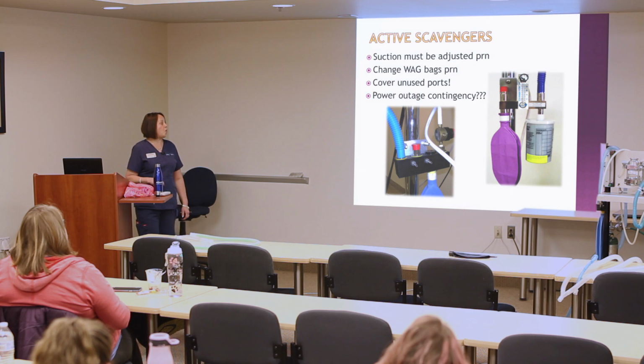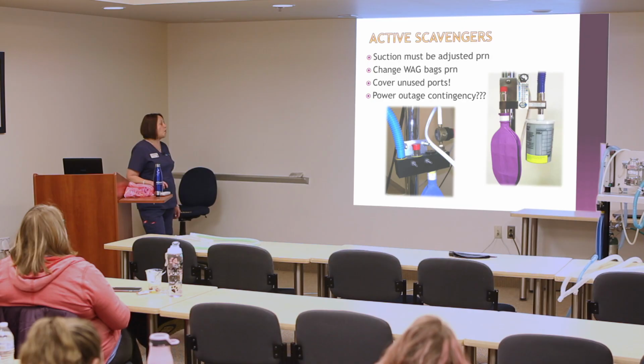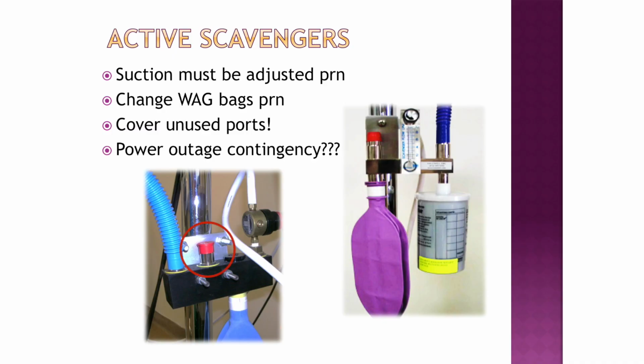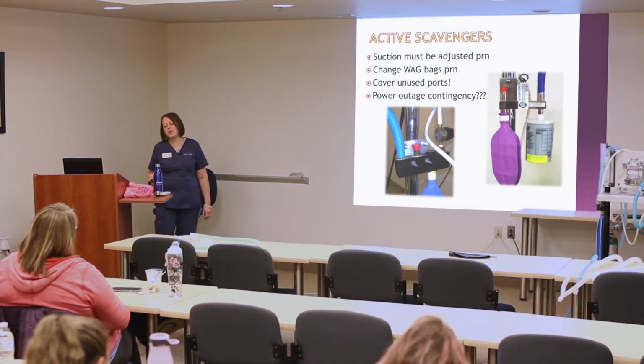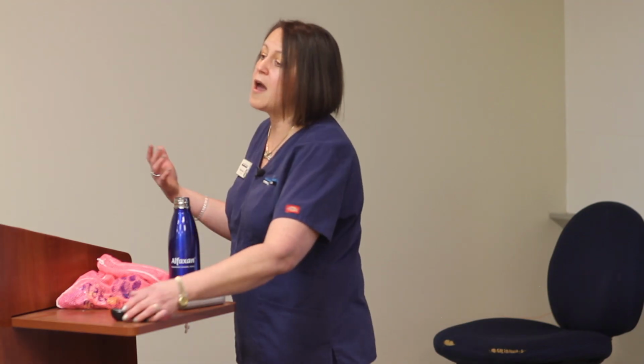And I do weigh these every week, and I throw them out when they weigh more than 110 grams. I basically weigh them when they're new, and then I put discard at, and I add 110 onto that number to be right in the middle of what they hold. Another really important thing about these active scavenger interfaces is if you're not using both of them, the open port right here has to have a red cap on it. If it doesn't have a red cap on it, that means waste anesthetic gases are coming out through this unused port.